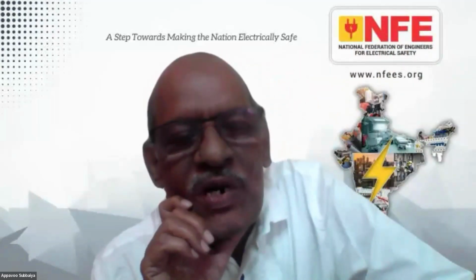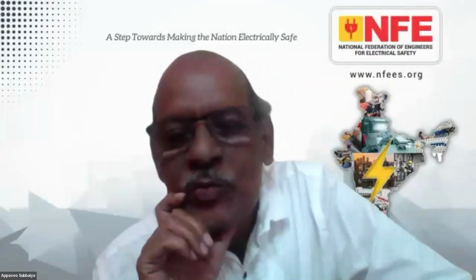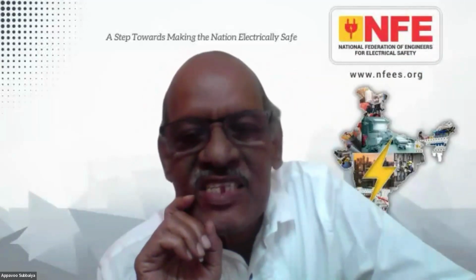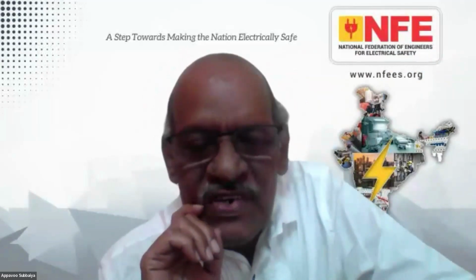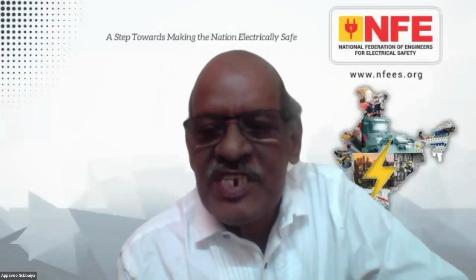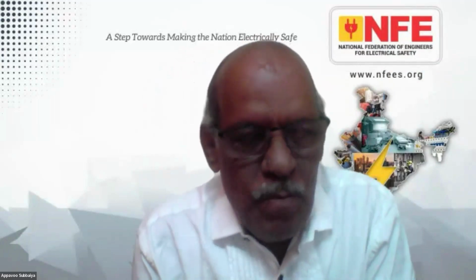So Manuvarki, I feel that the residual current device is an additional protection, but the basic thing - because after seeing a lot of electrocutions, especially in domestic premises, the regulatory body has insisted on this specific provision. Actually, if the supply is a TNS system, there is no need for a residual current device in the installation. But still, depending on the nature of electrical installations in our nation, the CEA has made a specific provision.